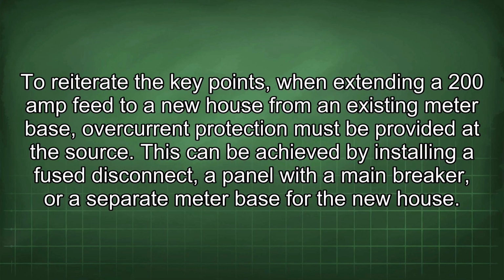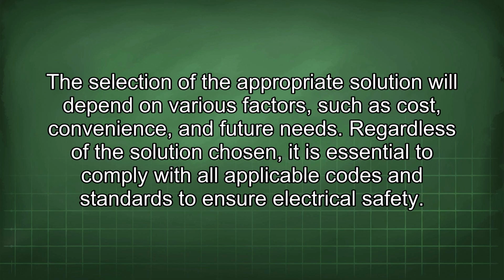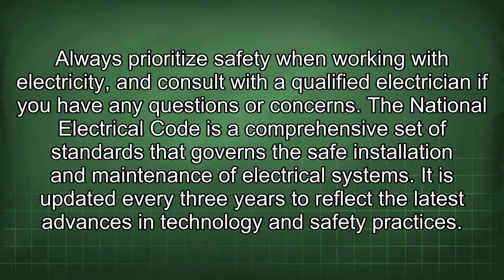To reiterate the key points, when extending a 200 amp feed to a new house from an existing meter base, overcurrent protection must be provided at the source. This can be achieved by installing a fuse disconnect, a panel with a main breaker, or a separate meter base for the new house. The selection of the appropriate solution will depend on various factors such as cost, convenience, and future needs. Regardless of the solution chosen, it is essential to comply with all applicable codes and standards to ensure electrical safety. Always prioritize safety when working with electricity, and consult with a qualified electrician if you have any questions or concerns.